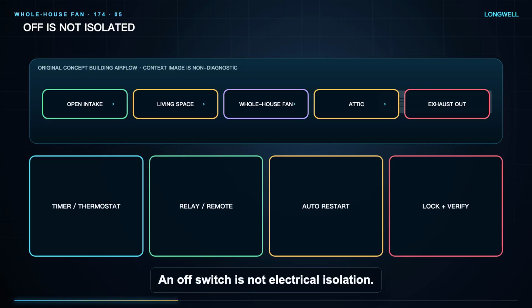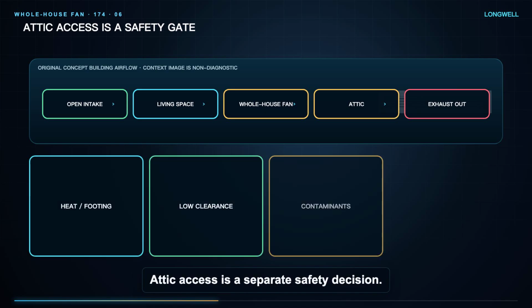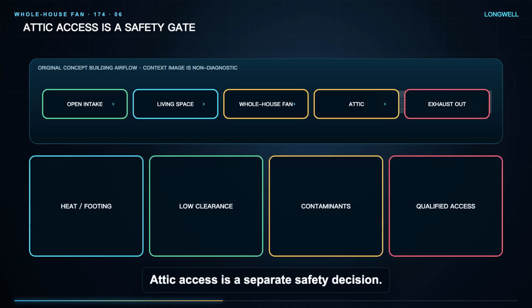An off switch is not electrical isolation. Whole house fans may have timers, thermostats, relays, remote controls, or automatic restart logic. A qualified person must identify every supply, isolate it, lock it against restart where required, and verify the safe state before opening equipment. Attic access is a separate safety decision.